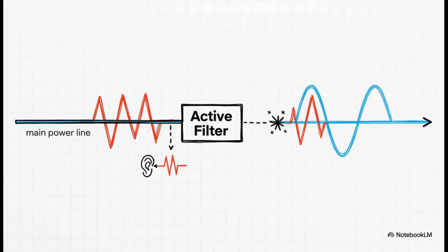And finally, we have the high-tech approach, an active filter. This thing is brilliant. It works almost exactly like a pair of noise-canceling headphones. It's constantly listening to the power line for any harmonic distortion, and then it injects the exact opposite, an anti-harmonic current, to cancel it out in real time. All that's left is that pure, clean waveform we want.